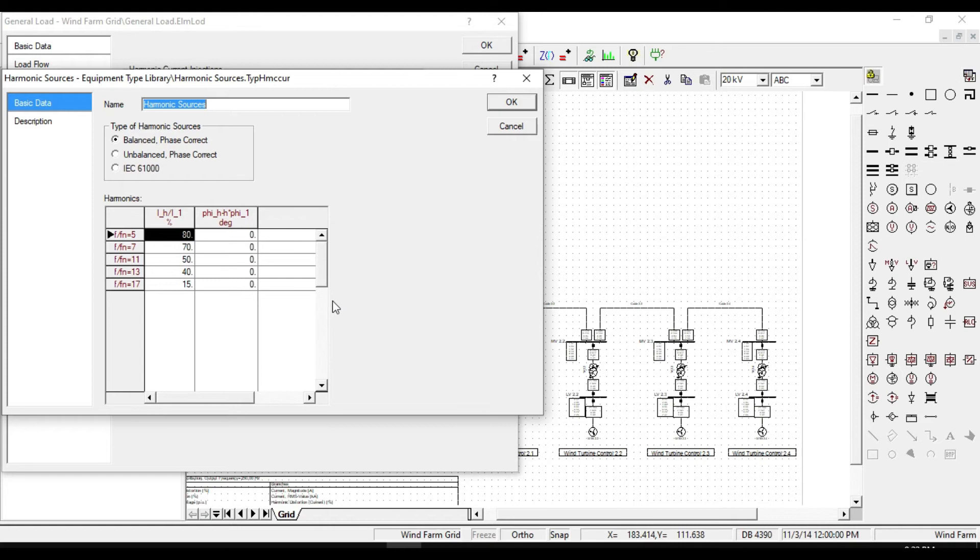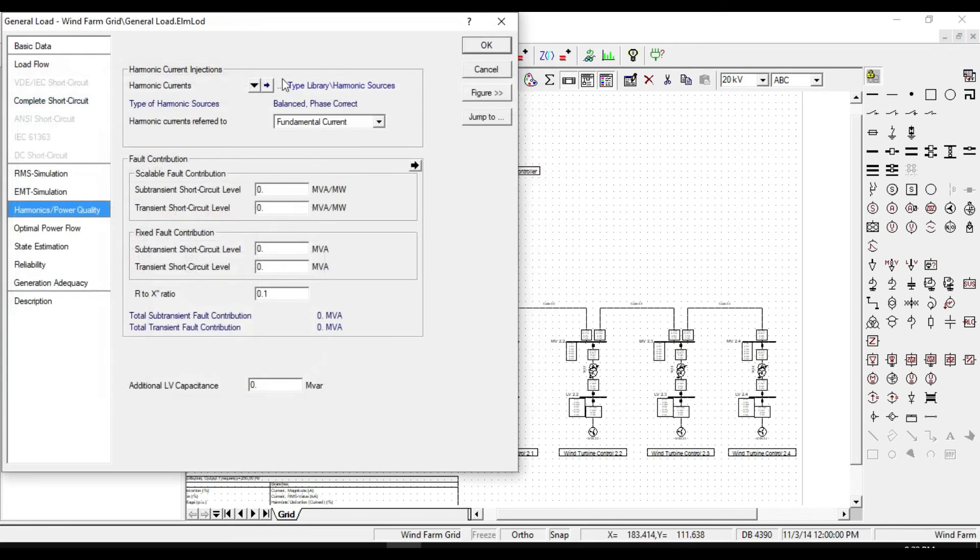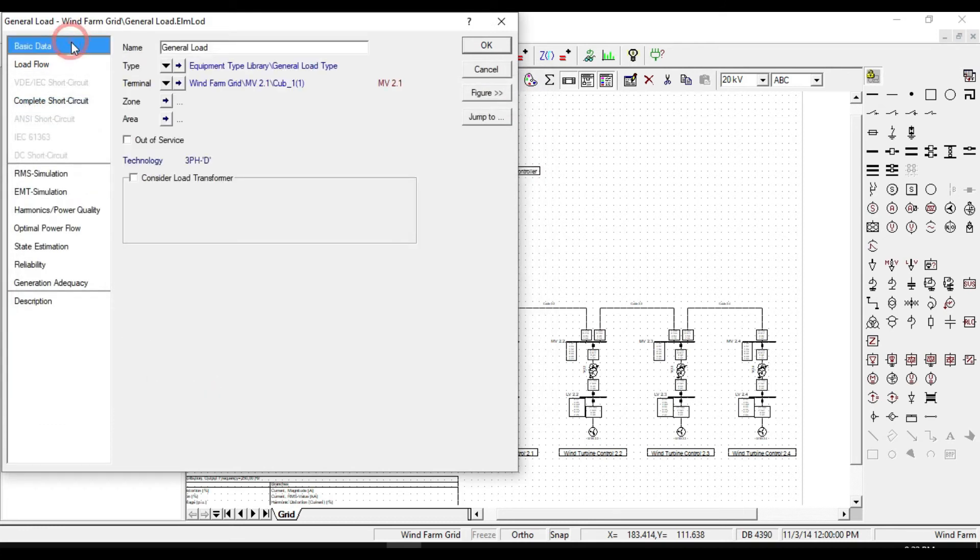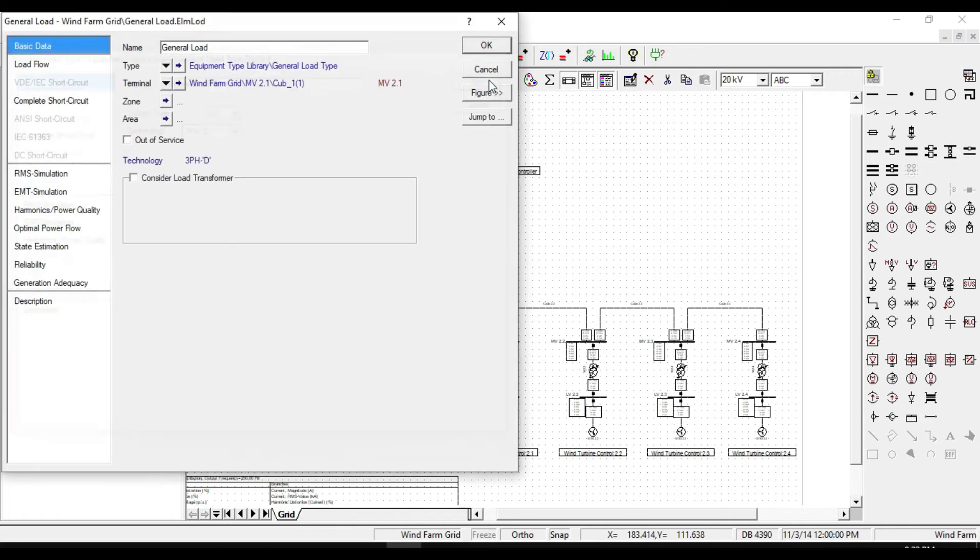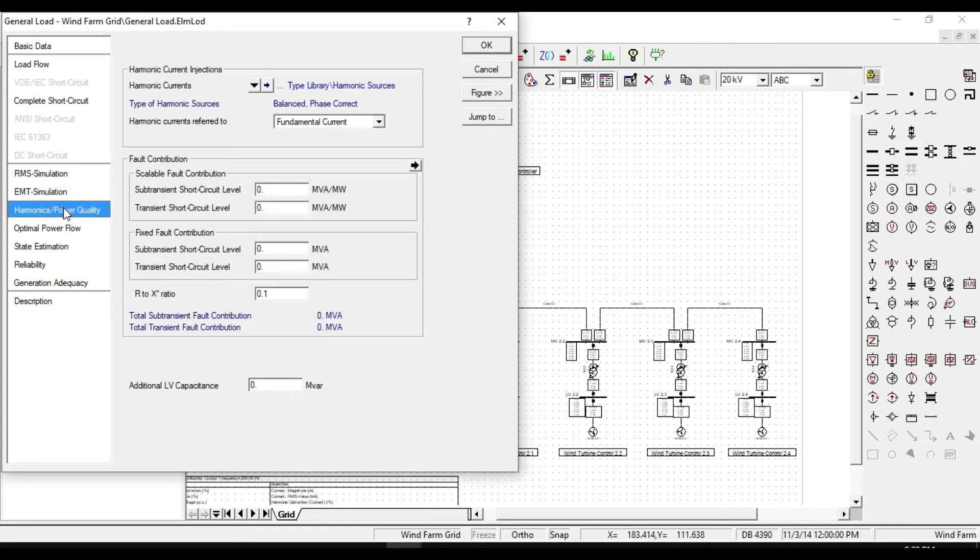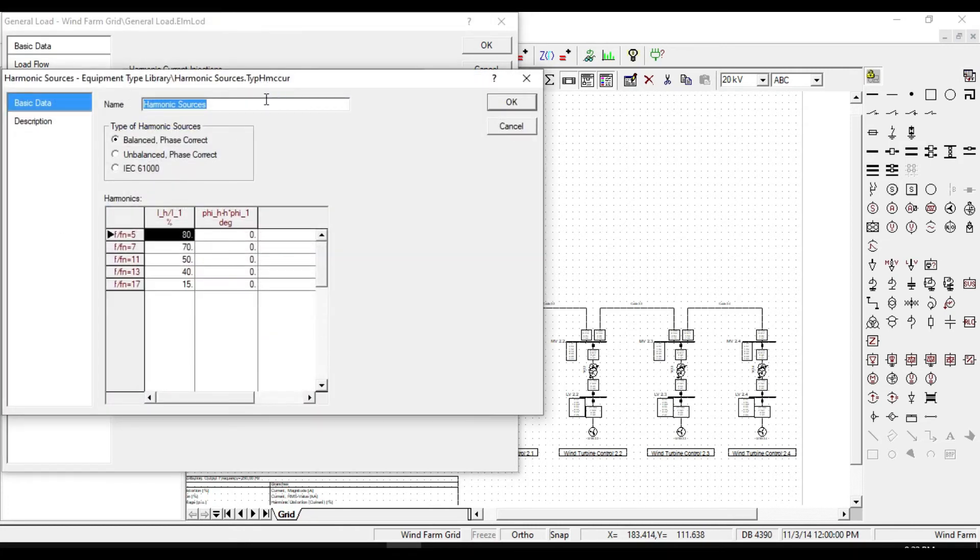Because it is a three symmetrical phases system. From the basic data, you can see that our system is defined as three phase. The reason why there is not any even harmonic is because our load is passive and there is no static generator connected to our load.